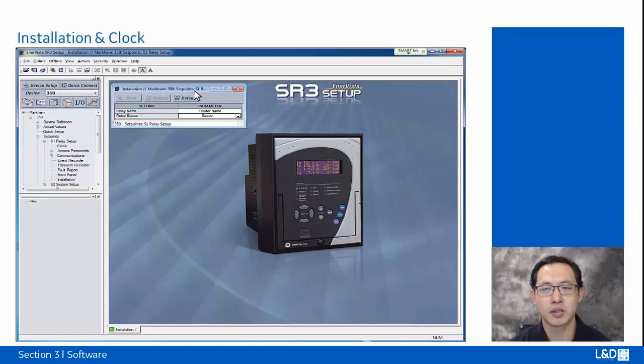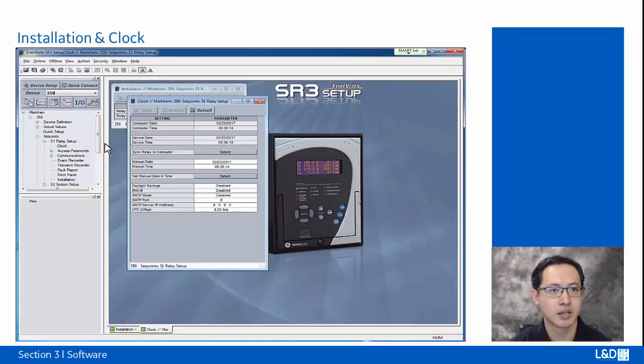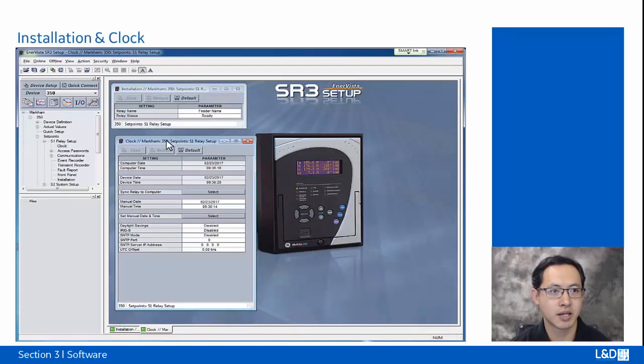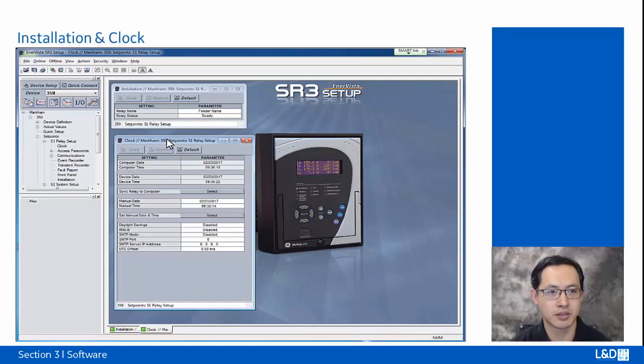Another setting for the initial setup is to set up the clock. Because if the clock is not synchronized with the computer, you get a target message, clock not synchronized. In this relay, it's already synchronized, but if you have a relay not synchronized, just open the clock and click Sync Relay to Computer and click Select. And then the computer date and time will be synchronized to the relay date and time.